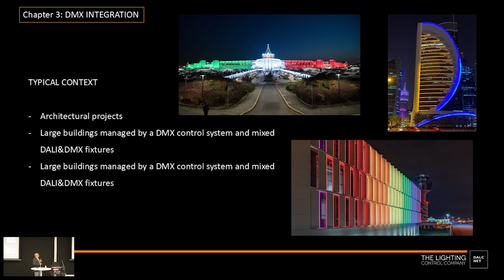I think it's important to speak about DMX integration because even if DALI is the most diffused protocol, in a lot of architectural projects there are hybrid requirements on the field. For example, in large buildings, sometimes wall washing luminaires or RGB effects on the facade are done in DMX because of the characteristics of those luminaires, while in the same building the interior lighting is managed by DALI luminaires, DALI sensors, and DALI push buttons as we've seen. So DMX and DALI integration is something real and quite common.